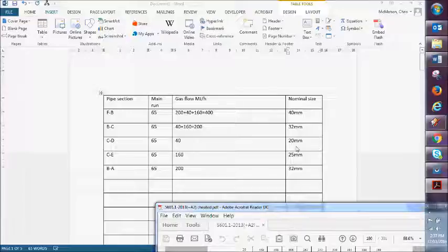Okay, and the reason for that is the inlet of the patio heater, say, will only be 15 mil. It's not very often you see an instantaneous with a 20 mil gas inlet. An oven only ever has a 15 mil because they're only little megajoules.